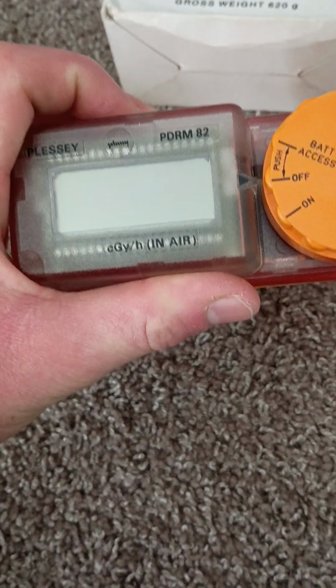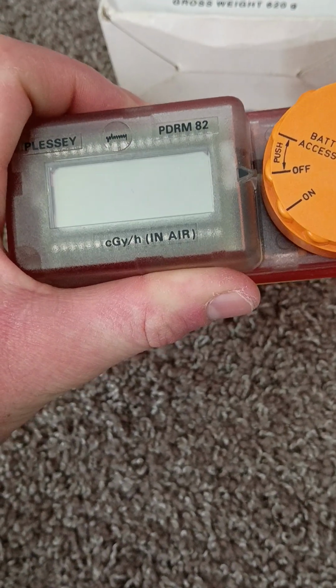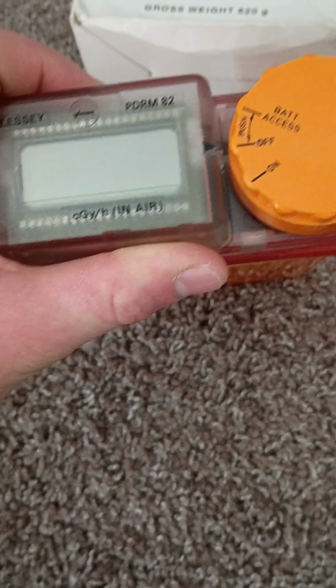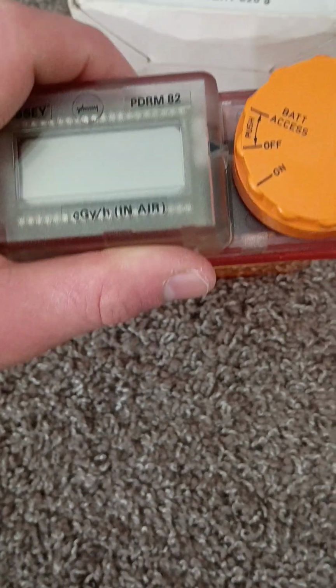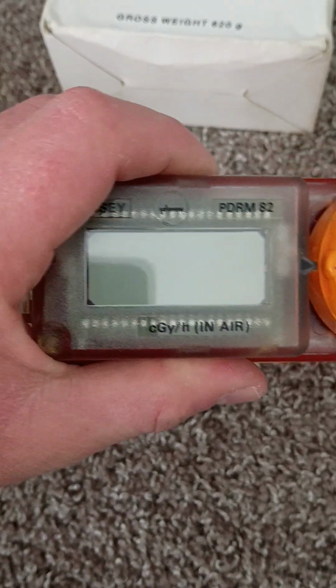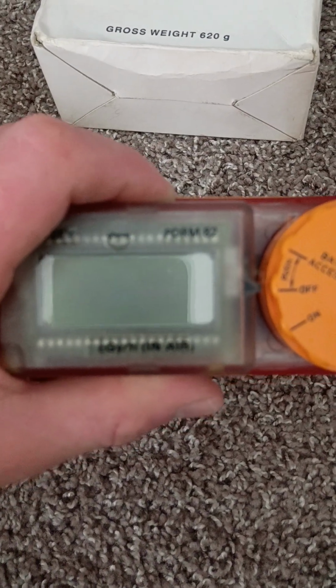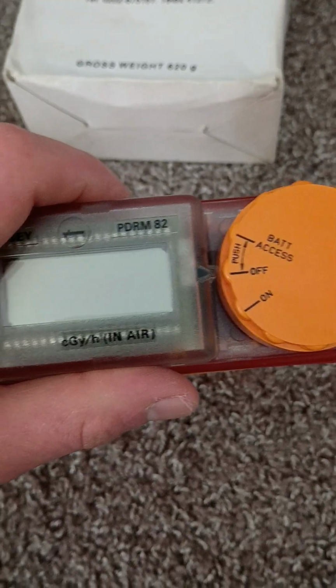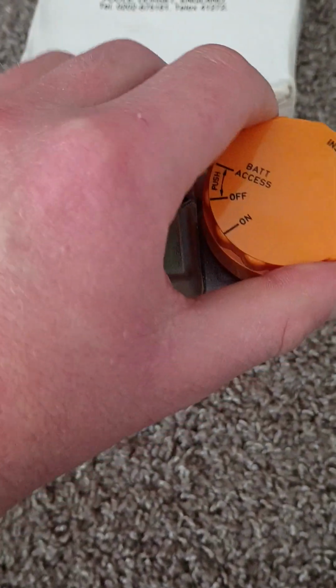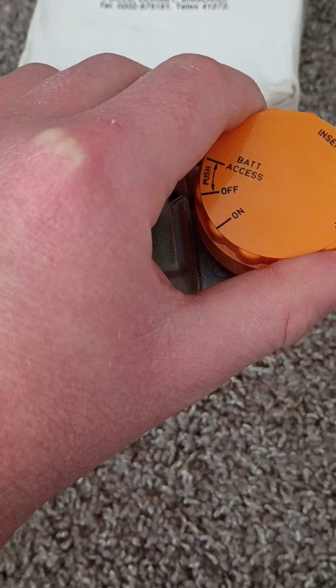This has a check source mounted on the inside of it as a part of the physical boot up process, which means that there's no waving of a probe. It is actually checking it every time you turn it on to ensure that it is working, and if it is not working, if the check source is dislodged, has failed, or if there's an electronic problem, it will not boot up. But a moment of truth, we'll see if it works.